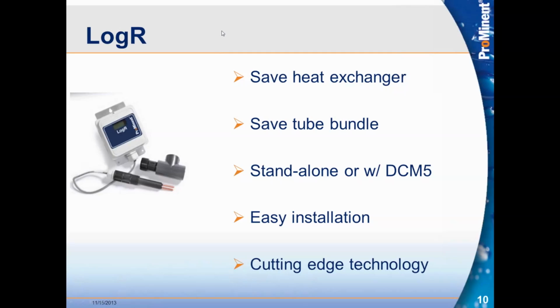Touching on the Log-R system, this is derived out of our industrial cooling tower segment. To set this up a little bit, what a Log-R does is a real-time, cutting-edge way to tell if the water is going to be corrosive to a certain type of metal. Now, why is this important? I can't tell you how many times in the past I've talked to operators who are going through big 2 million, 5 million BTU heat exchangers or tube bundles on their systems, simply because the water gets corrosive and nobody really knows about it.